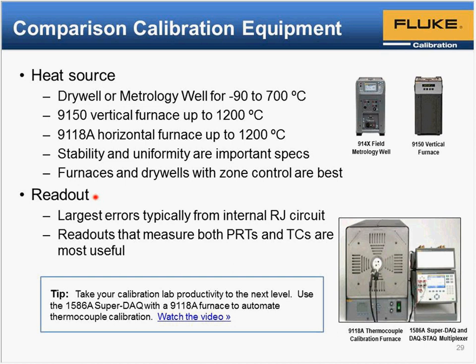Thermocouple readouts, of course, have the thermocouple math built into them, and there are different techniques for entering either tables for a calibrated thermocouple, or calibration coefficients that can be entered for the thermocouple, and there really isn't an industry standard, so it can be a little frustrating to use. I get a lot of questions from people asking for help converting. I have a thermocouple calibrated at NIST. They gave me the function coefficients. I don't know how to put them in my readout. Can you help me out with this? And anyway, it gets all complicated. Unfortunately, there isn't a clean standard like there is for PRTs with the ITS-90 equation coefficients. So let's see.